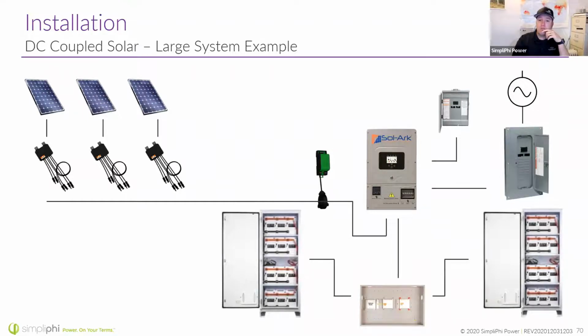Here is a Sol-Ark DC coupled large example system. Here's the Tigo rapid shutdown transmitter, giving the keep alive signal to these Tigo TS4F, I think they are, on our solar panels. So we have DC coming down off the roof, DC feeding into that Sol-Ark, DC charging the batteries. Only when we need to feed back to the grid or feed critical loads do we turn it back into AC. That Sol-Ark will feed this critical load subpanel. Over here, non-backed up loads with grid.